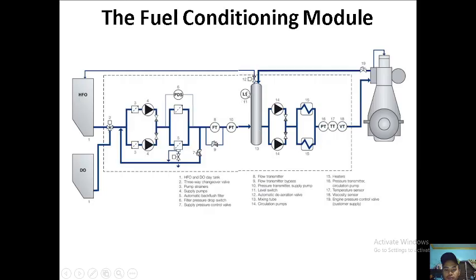Number 11 is the level switch. Number 12 is the automatic deaeration valve. It's a deaerator, it removes air. 13 is the mixing tube or the vent tank. 14 is the circulation pump or the booster pump. And then we have 15, heaters. 16 is the pressure transmitter. 17 is the temperature transmitter. 18 is the viscosity transmitter or viscosity sensor. And we have here the engine. 19 is the engine pressure control valve. So that is our fuel conditioning module.